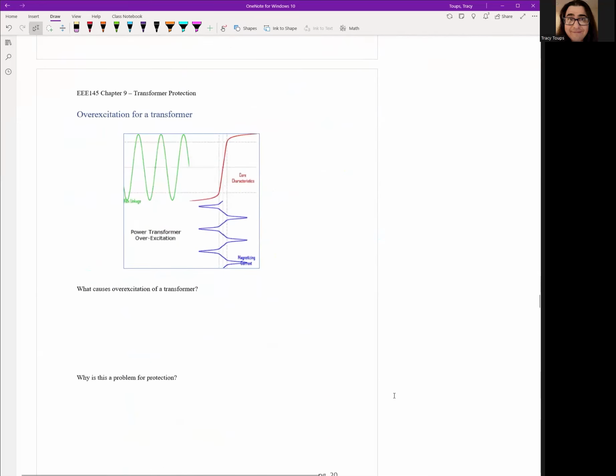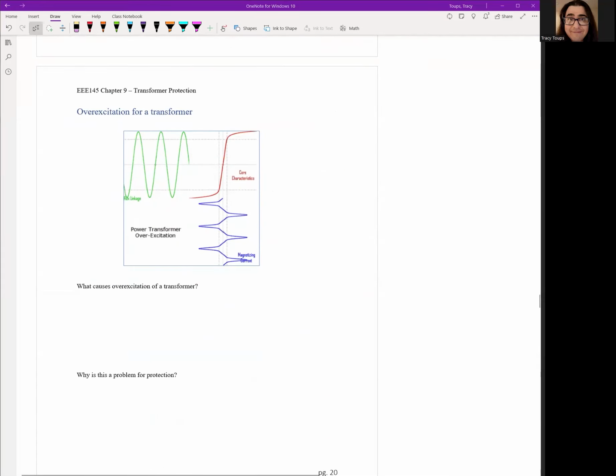Next, let's do overexcitation of a transformer. Unfortunately, this thing doesn't play. The idea is the core characteristic is your hysteresis loop. The big thing you need to see here is when you apply too much voltage, you have distorted current. Notice the current is not purely sinusoidal. It's kind of bent a little bit and has spikes everywhere. That's not good. You're going to cause some problems, especially on the turns ratio coming in and out and the readings on the CT.